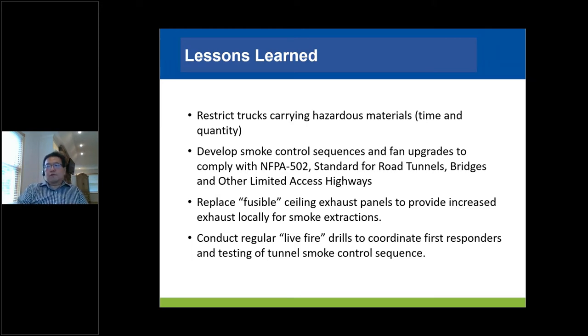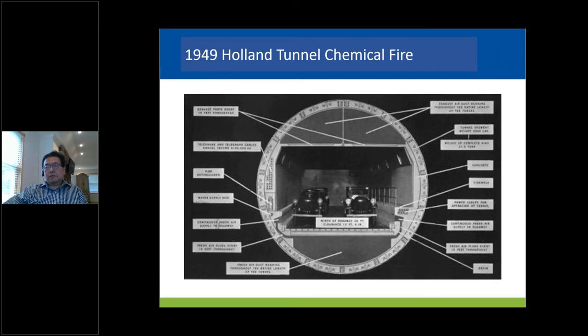This also enables the first responders to get in front of the fire and put it out. Another creative idea that came out was fusible ceiling exhaust panels on top of the exhaust plenum. If there's a fire, these panels melt and create a larger opening, giving a much higher exhaust rate right over where the fire occurs.